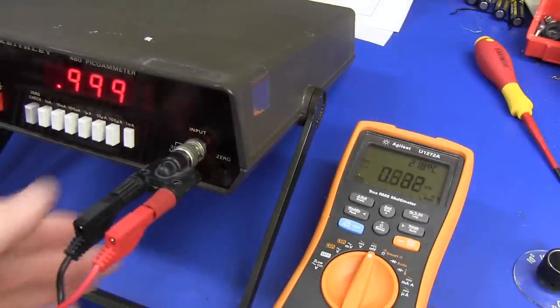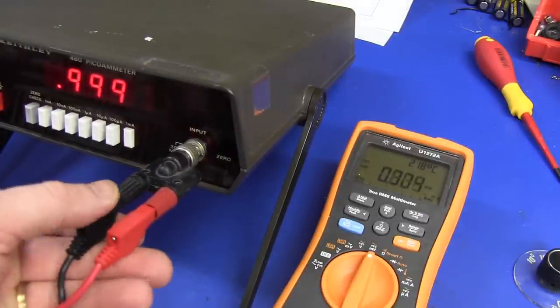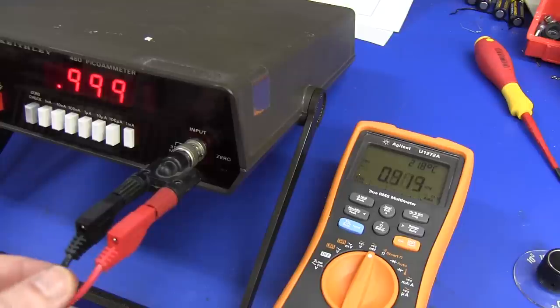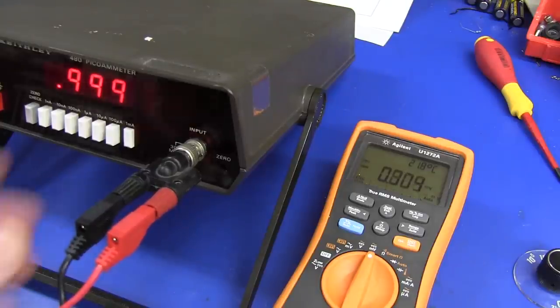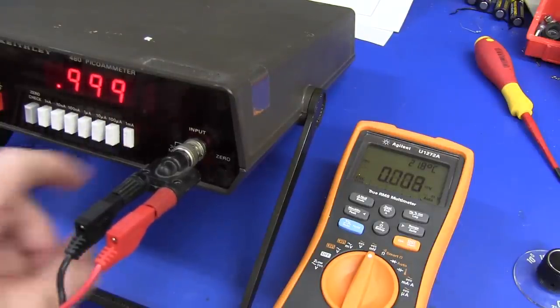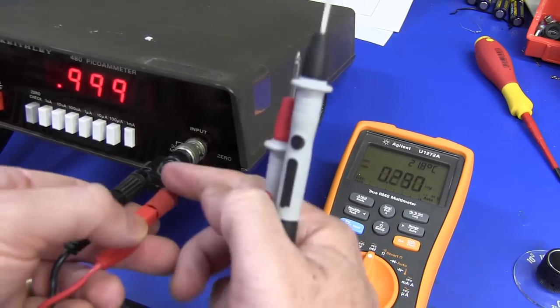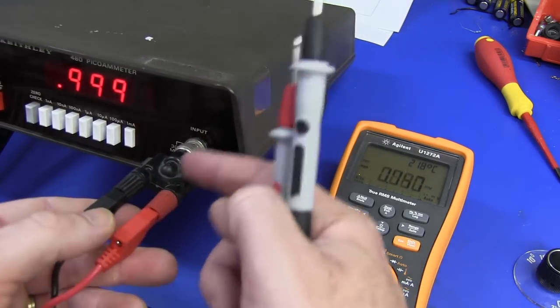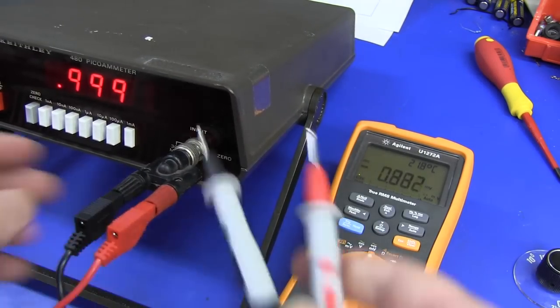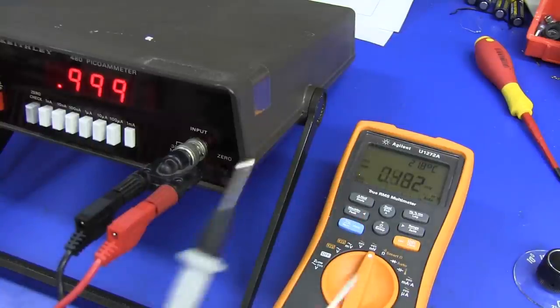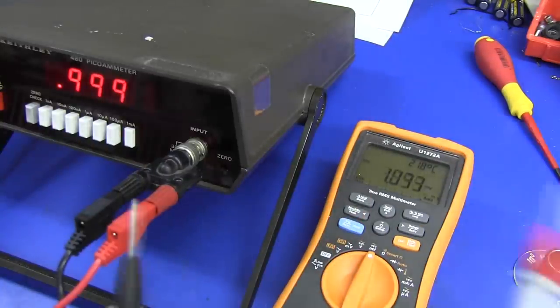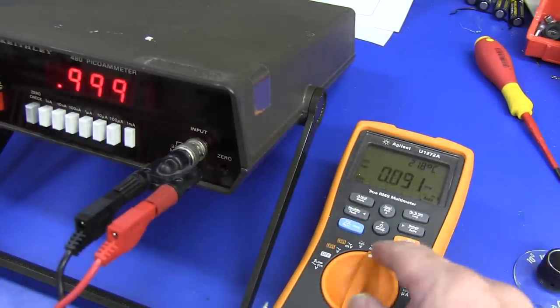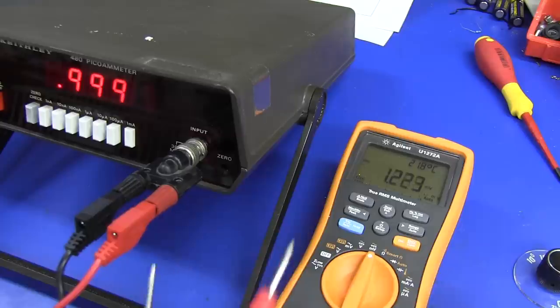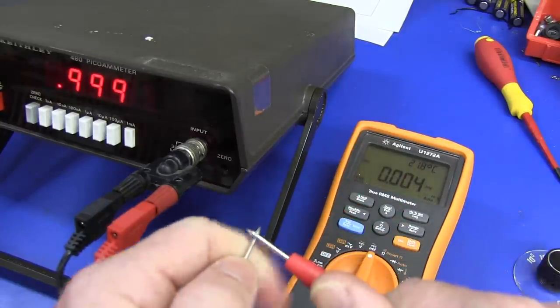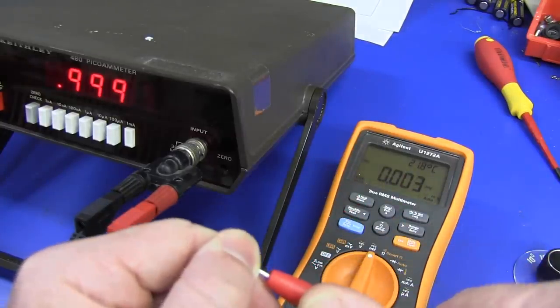And just for kicks, let's make sure the burden voltage is less than the 200 microvolts claimed. So what I've got is I'm feeding in 1 milliamp here, and I've got a banana to BNC jack here, so that we can get in here with our meter and probe it. Now I'm going to use my Agilent U1272A because it's got the 50 millivolt range, so the resolution can go all the way down to 1 microvolt.